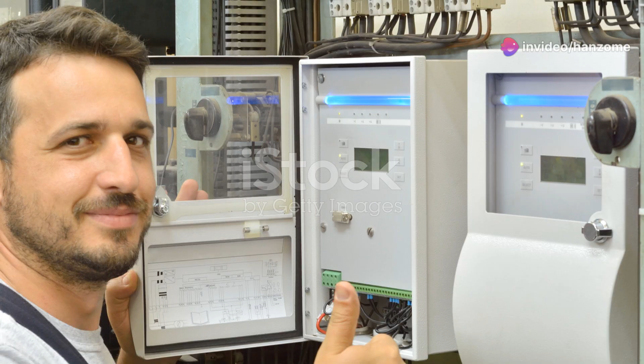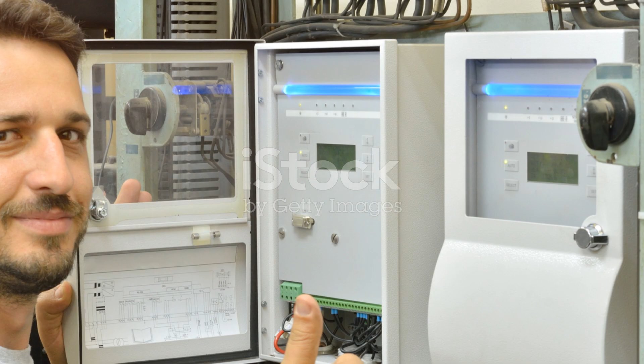Now, choosing the right circuit breaker size is crucial. Always opt for a breaker that can handle more current than your appliance draws. For our 1200-watt microwave, a 15-ampere breaker would be ideal. This ensures it won't trip unnecessarily, but will still protect your home.